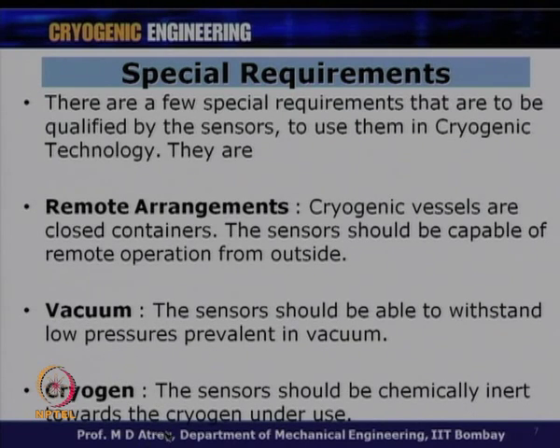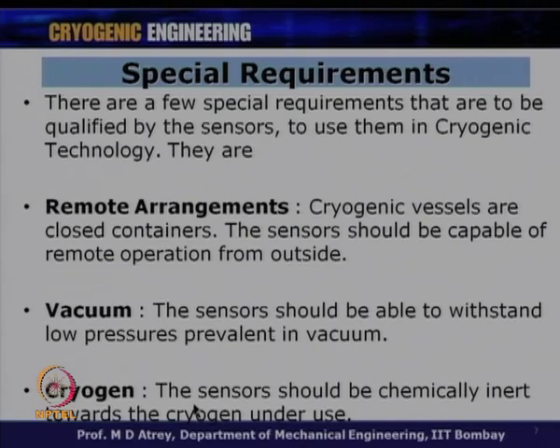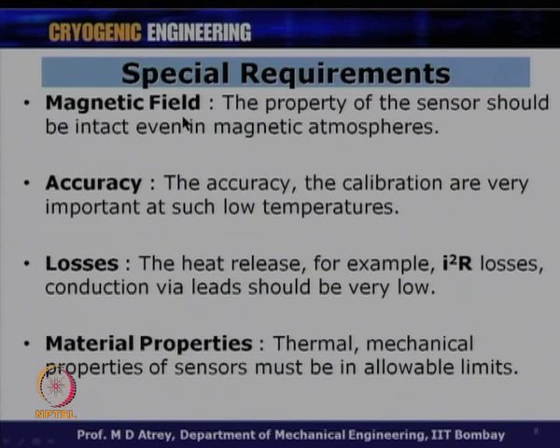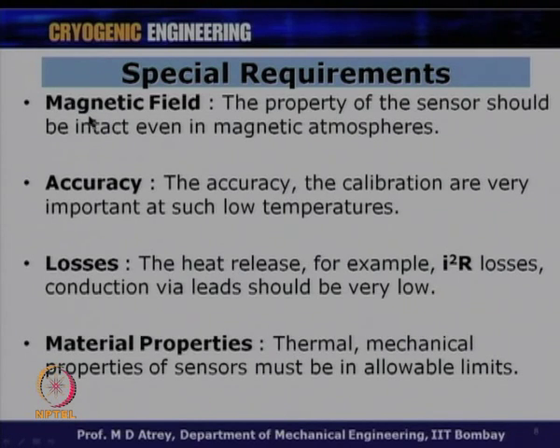The sensor material must be chemically inert toward the cryogen in use—it should not react with liquid nitrogen or liquid hydrocarbons. Some sensors must work in magnetic fields, where sensor properties must remain intact. For example, silicon diodes cannot be used in magnetic field environments—Cernox sensors must be used instead for temperature measurement. This is a critical consideration when designing for magnetic field environments such as MRI.